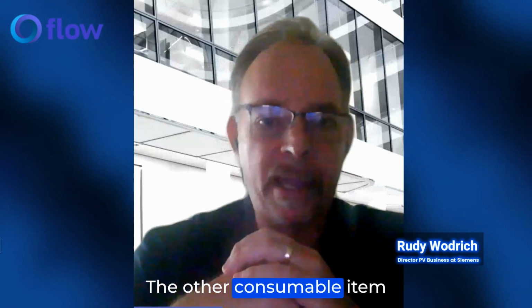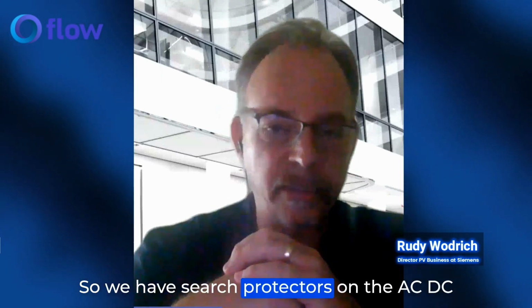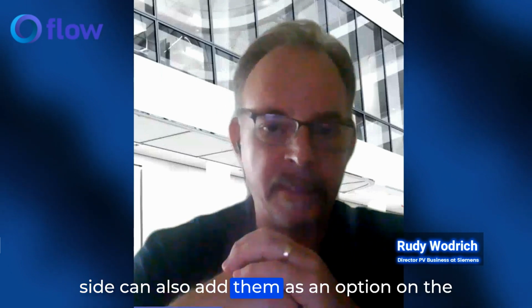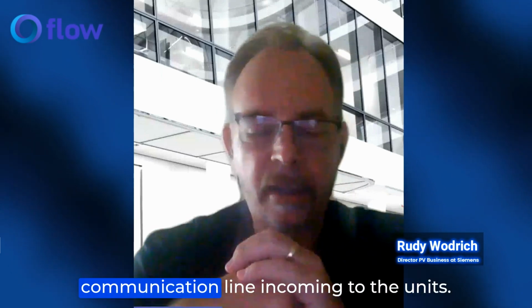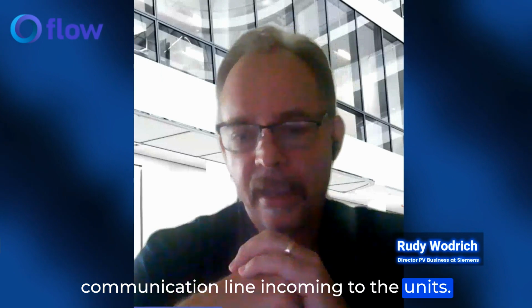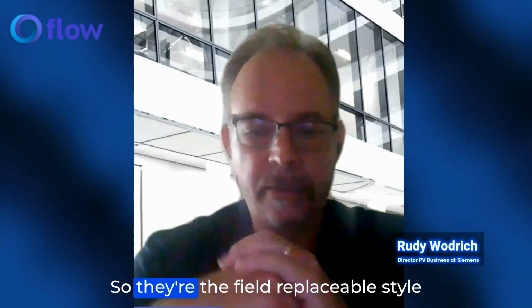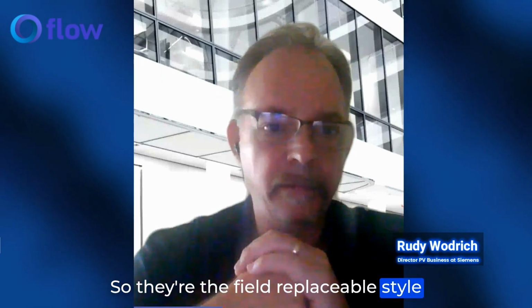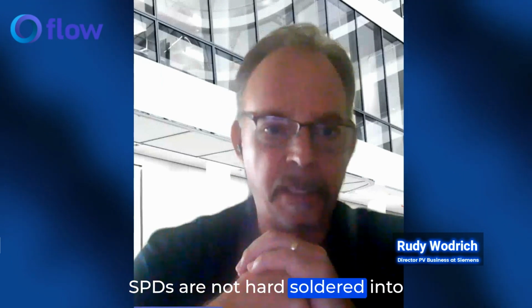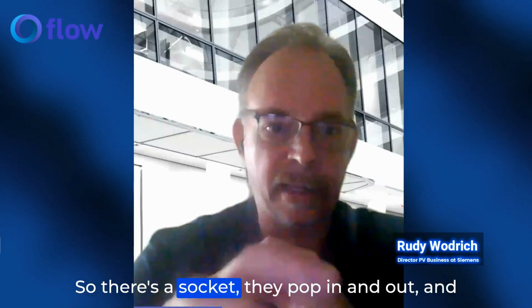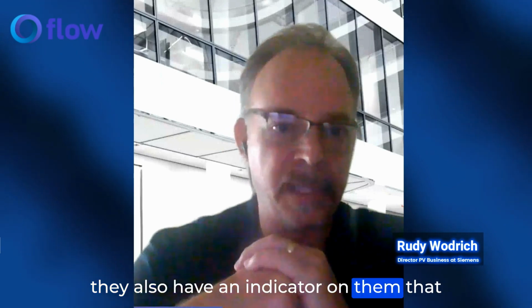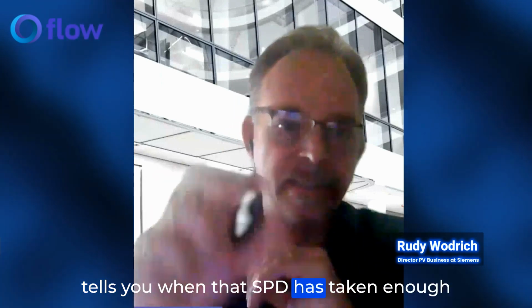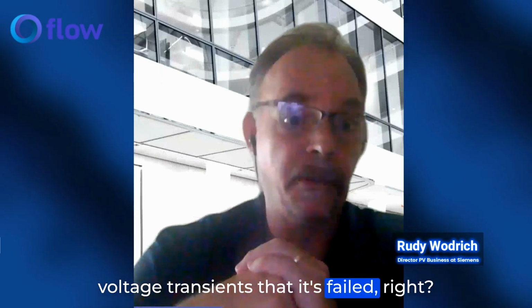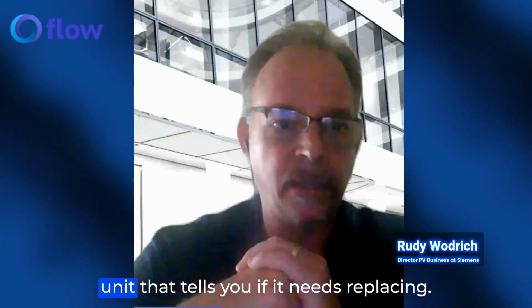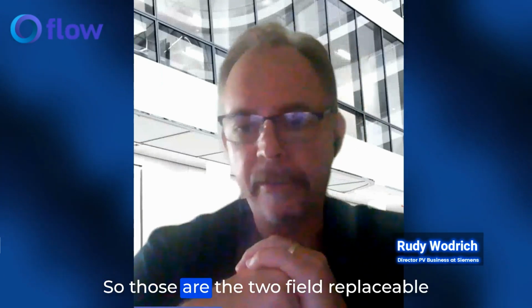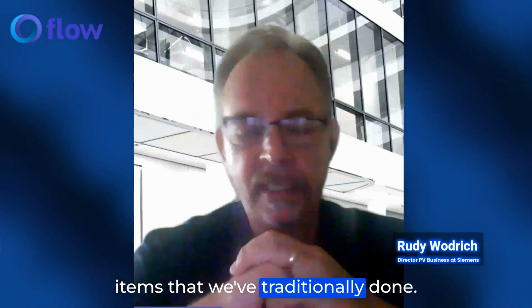The other consumable item is surge protectors. We have surge protectors on the AC and DC side, and can also add them as an option on the communication line incoming to the units. Those all use socket connectors—they're the field replaceable style SPDs, not hard soldered into position on the printed circuit board. There's a socket, they pop in and out, and they have an indicator that tells you when that SPD has taken enough voltage transients that it's failed. So there's a visual indicator on the unit that tells you if it needs replacing. Those are the 2 field replaceable items we've traditionally done.